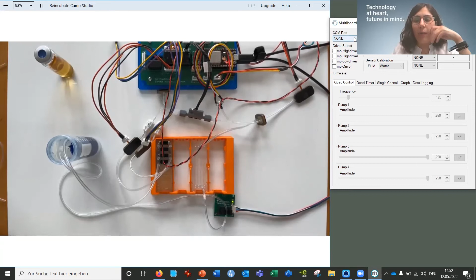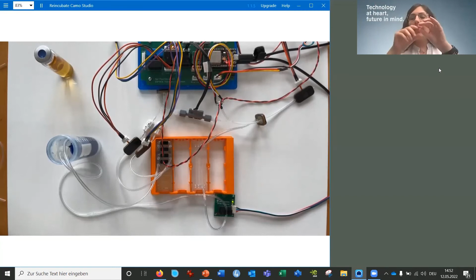This is one of our latest liquid flow sensors. Let me describe it in my Italian way with gestures. The measurement principle is a microthermal principle. You have a heater in the middle, on top of a membrane, and on the side two temperature sensors. When the liquid is flowing, it carries the heat generated by the heater at a speed related to how fast the fluid is moving inside the channel.